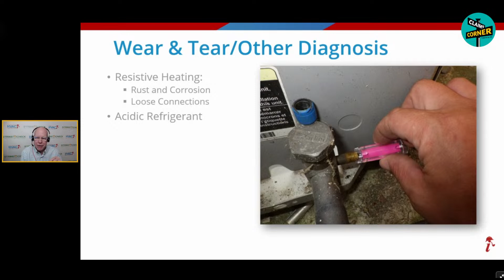We can't have any contaminants in the refrigerant. If we do, it becomes acidic and then the compressor fails. That does not happen suddenly and accidentally - that happens over time, and it is not caused by lightning or surge. So if you have acidic refrigerant that has frozen up or burned up your compressor, and someone says that lightning was so bad or so hot it turned the refrigerant into acid, I'm here to tell you that can't happen. That doesn't happen that way. Acidic refrigerant is from contaminants that happens over time.